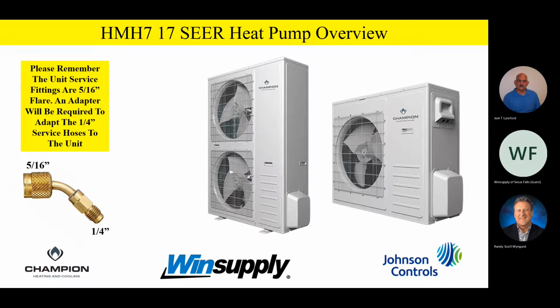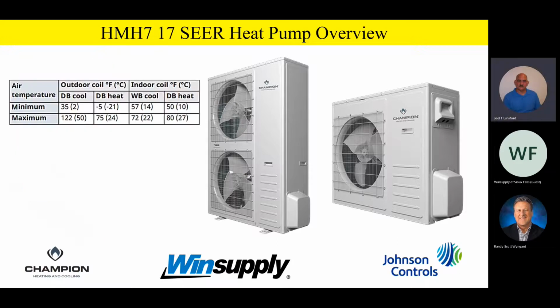Another question we get asked quite a bit on the new HMH7 SEER heat pump is, how low will it cool to and what's the maximum it'll cool to? Well, this little chart right here is right out of the install information. It'll go down to 35 degrees for cooling and up to 122 for cooling. Then in the heating mode of operation on the outdoor coil, it'll heat all the way down to -5, where it starts to lock out. It'll lock out at -5 or -6. So that's a pretty good range if you think about it in the heating and cooling mode both for the outdoor unit.